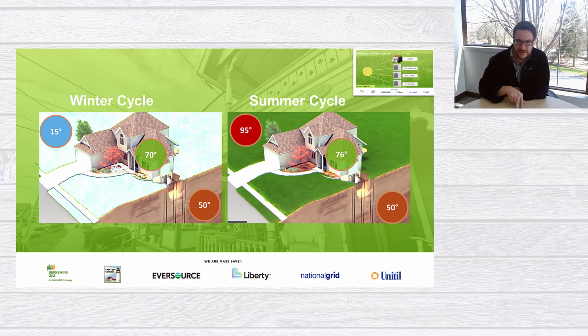With a geothermal system, looking at this chart, 50 degrees underground is warmer than 47 degrees outside. Does a geothermal system just always run at the best coefficient of performance that an air source heat pump system does? The answer is more or less yes.